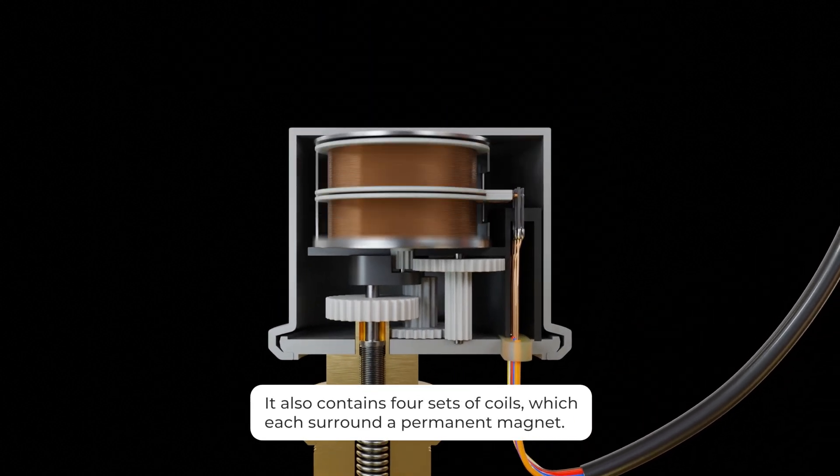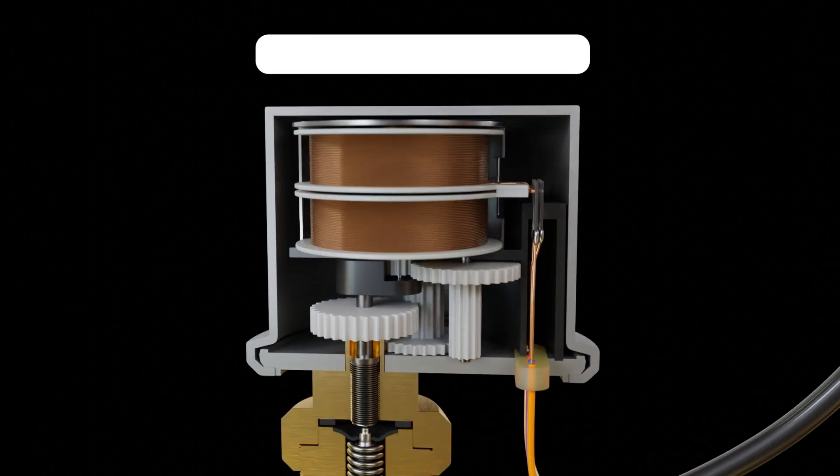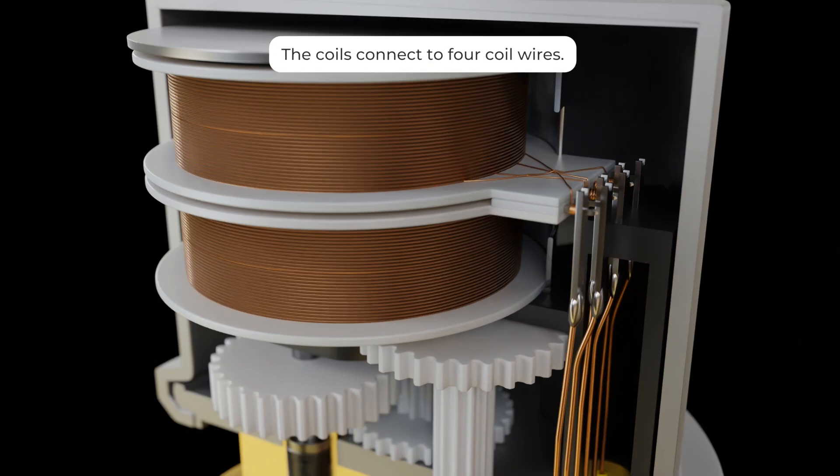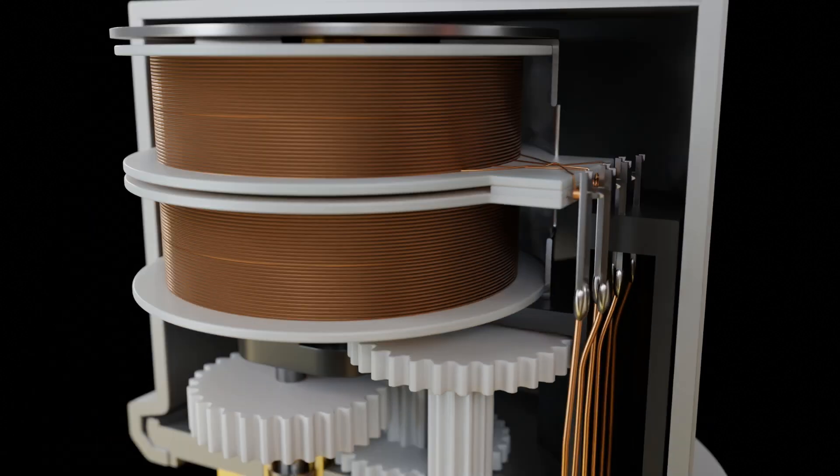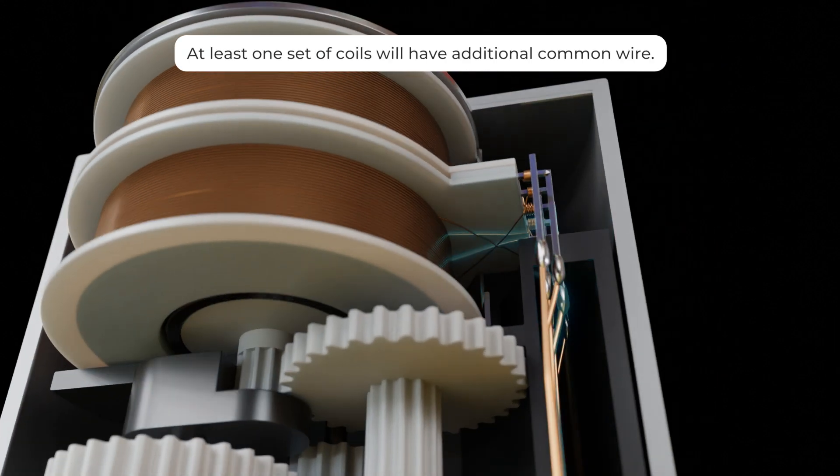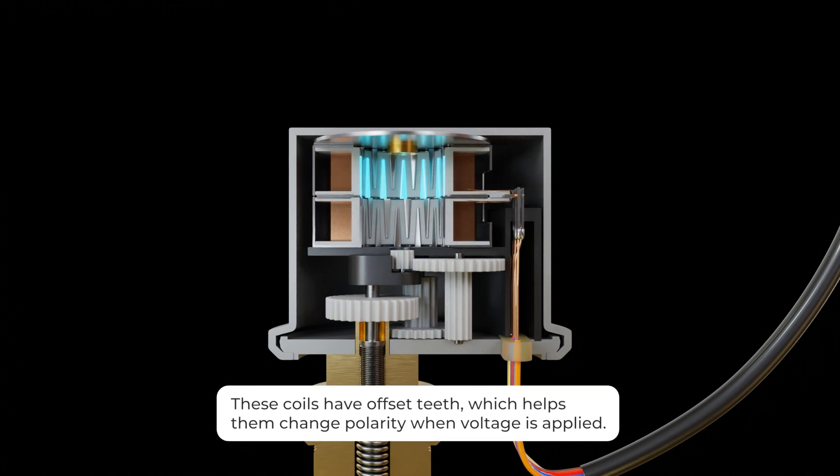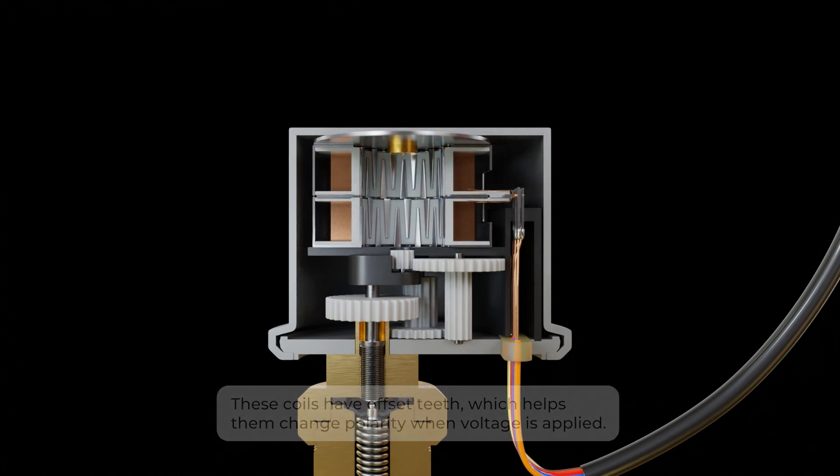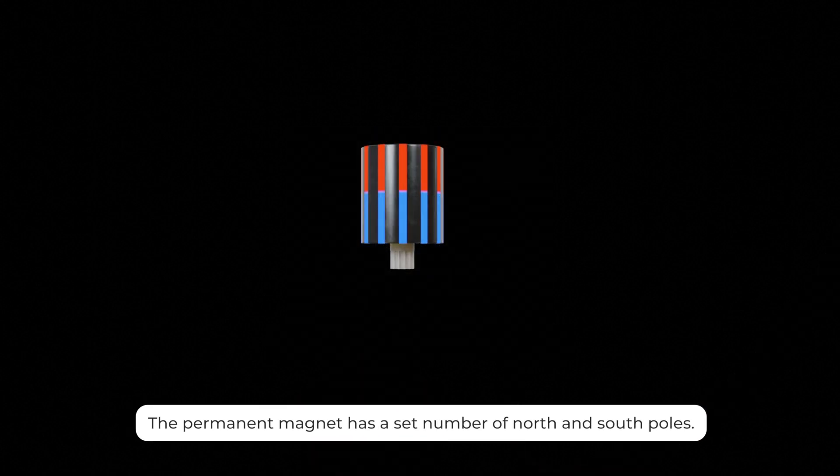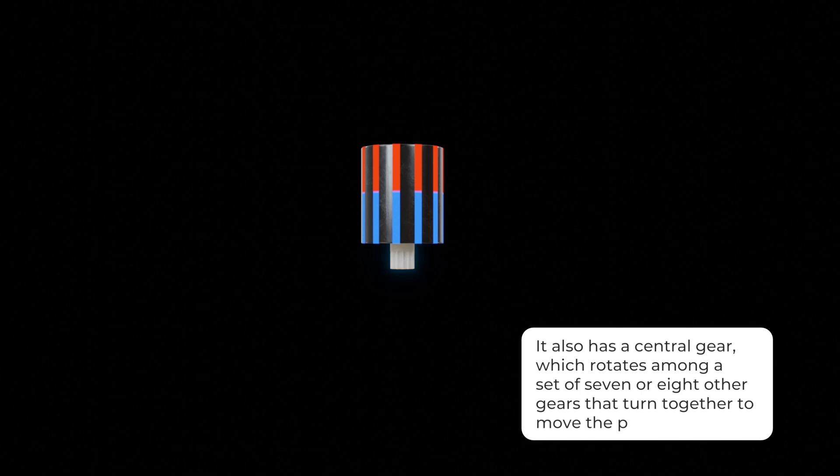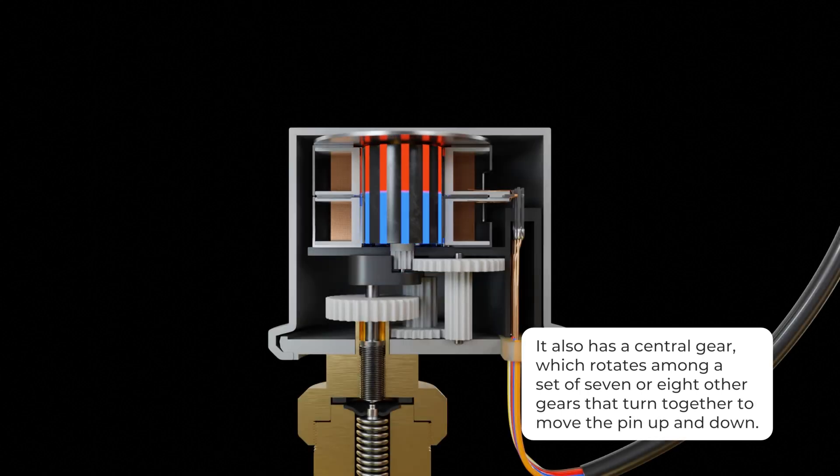It also contains four sets of coils which each surround a permanent magnet and connect to four coil wires and at least one set of coils will have an additional common wire. These coils have offset teeth which helps them change polarity when voltage is applied. The permanent magnet has a set number of north and south poles as well as a central gear which rotates among a set of seven or eight other gears that turn together to move the pin up and down.